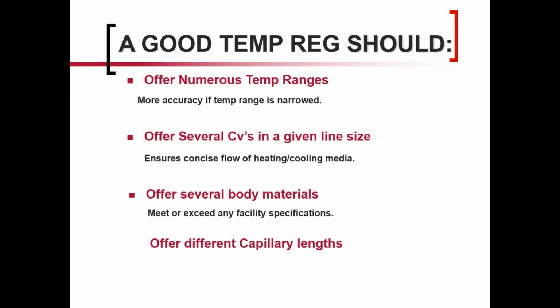Offers numerous temperature ranges. So again, there's various fill fluids depending on the temperature you're looking for. If you use a fluid that can control between 50 and 200, it's going to be a lot harder to dial it in to the exact temperature that you want. So if you have more ranges available, maybe 50 to 80, 75 to 100, then the narrower range will help you dial in a little bit more accuracy. And again, when people have issues, especially perception issues with these, it's sloppy temperature control. So, if you pick the right range and it's narrower, then you've got a better chance of hitting your temperature target. Offer several CVs in a given line size.